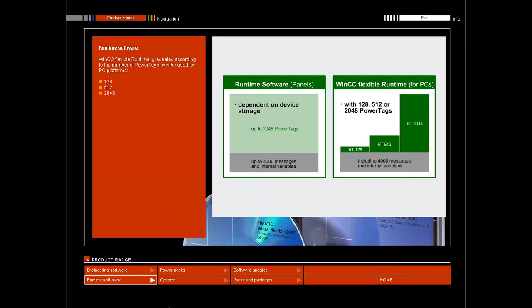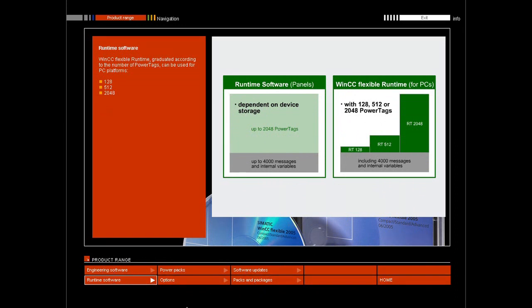For PC platforms, you can use WinCC Flexible Runtime, graduated according to the number of power tags. Only variables which have a process interface to the controller count as power tags. Variables without process interface, constant limit values of variables, as well as up to 4000 messages are also available as enhancements to system performance.